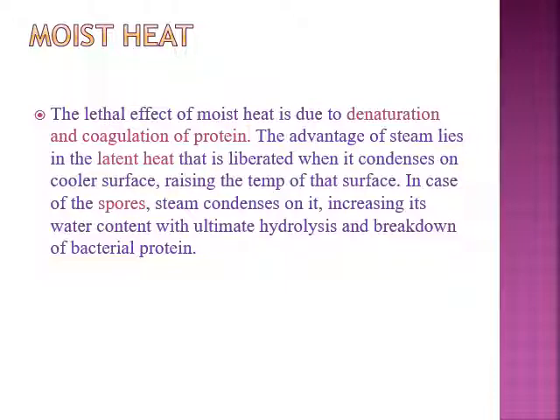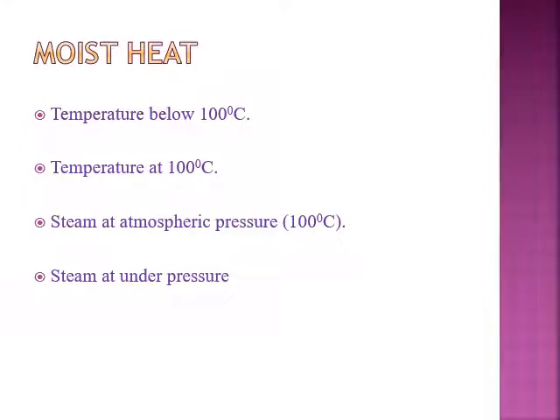The lethal effect of moist heat is due to denaturation and coagulation of protein. The advantage of steam lies in the latent heat that is liberated when it condenses on a cooler surface, raising the temperature of that surface. In this process, steam condenses on it, increasing its water content with the ultimate hydrolysis and breakdown of the bacterial protein. So in moist heat, there is a temperature below 100 degrees or at 100 degrees, steam at atmospheric pressure, that is 100 degrees Celsius, and steam under pressure.